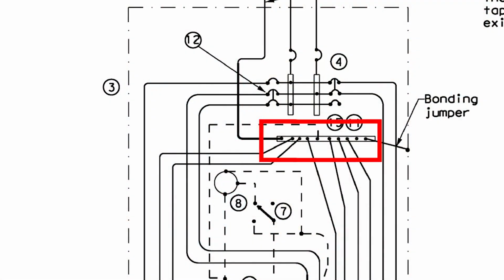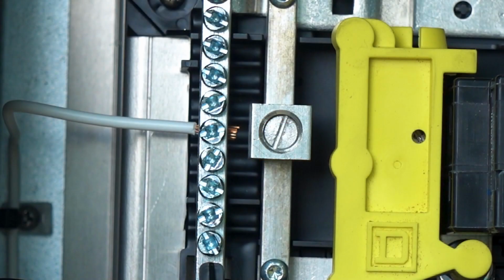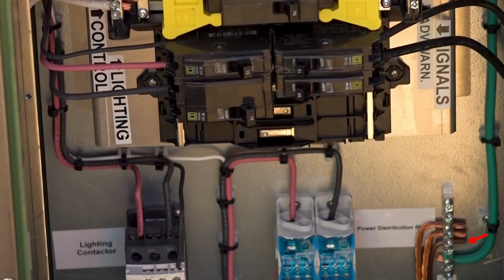The Type D service is shown on the schematic diagram with a single bus bar, to which is connected the grounded service entrance conductor, also called the neutral conductor. All white insulated neutrals from the branch circuits will also be connected to the bar. The electrical service grounding electrode conductor will also be connected to the bus bar. This is a solid number 6 AWG bare copper conductor, the other end of which is connected to the ground rod or to the steel support pole itself. All equipment grounding conductors will also be terminated to this bus.